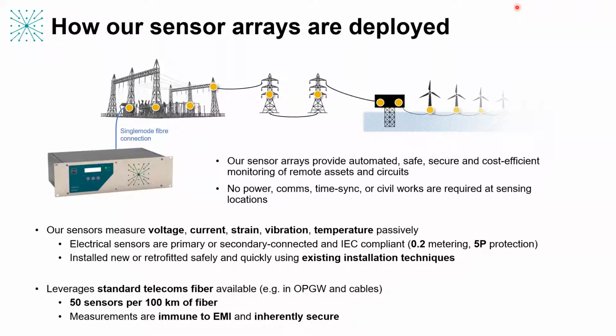So we use standard telecoms fiber. No specialist fiber is needed. No new fiber needs to be laid. If you've got fiber in your system, you already have the infrastructure that is required to deploy our sensor networks. So we can use the fiber that's in OPGW, for example, or in subsea cables. We can deploy 50 sensors per single fiber core. It's a single-ended scheme, so it doesn't need to be connected from both ends. And we can reach out over 100 kilometers and gather in multiple measurements. And we'll talk later about what that really enables us to do.